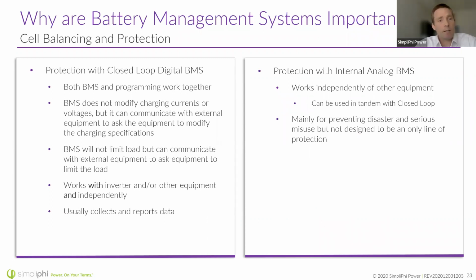Other battery management systems have protection through closed loop communication. The main function of a BMS is to keep a system working properly, as well as to protect the battery itself. Closed loop communications allow a BMS, as it's monitoring currents, voltages, and even temperatures inside the battery stacks, to provide that information—voltages, capacities, state of charge, state of health, etc.—to the charging equipment or the discharging equipment, the inverter, the loads, to limit the amount of power that comes out of the battery. So the battery can communicate with systems, and typically this communication is done with CAN bus.